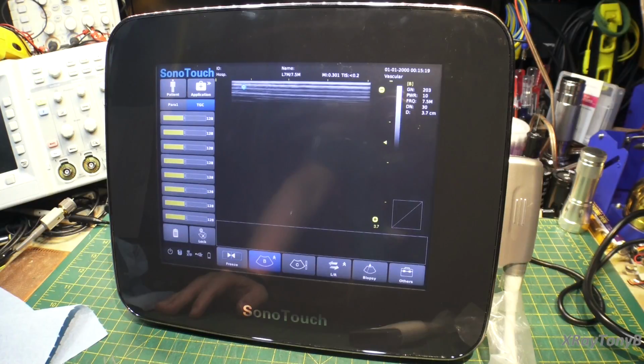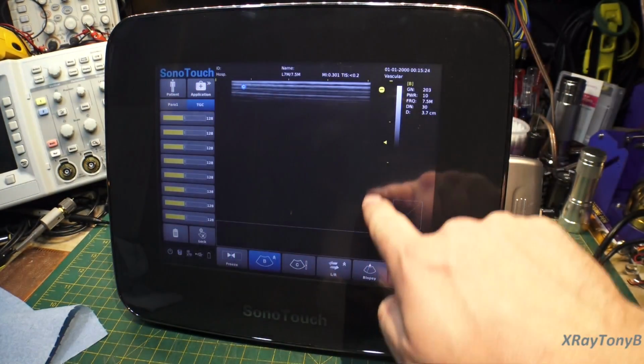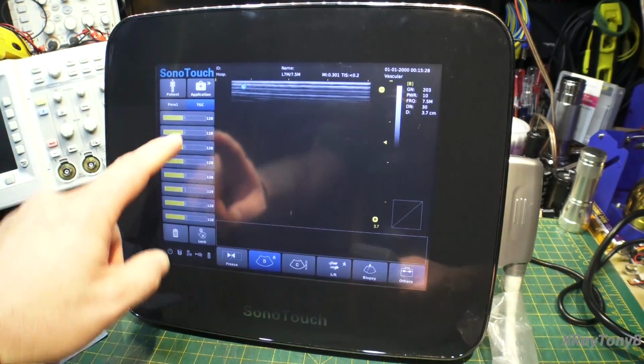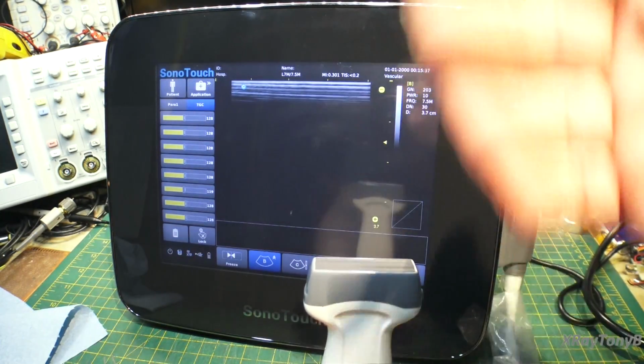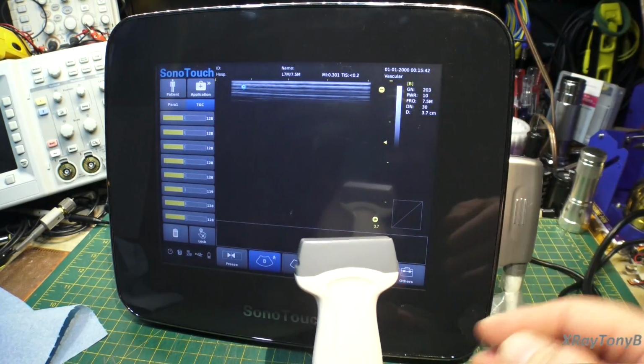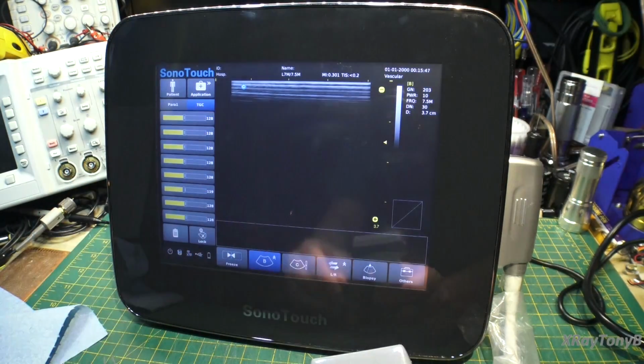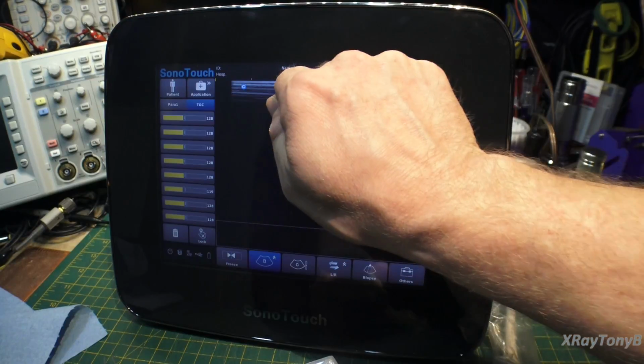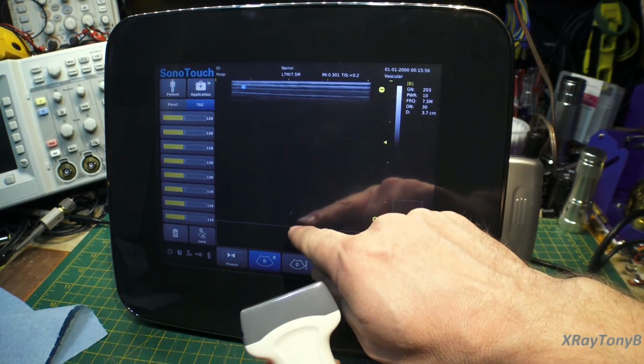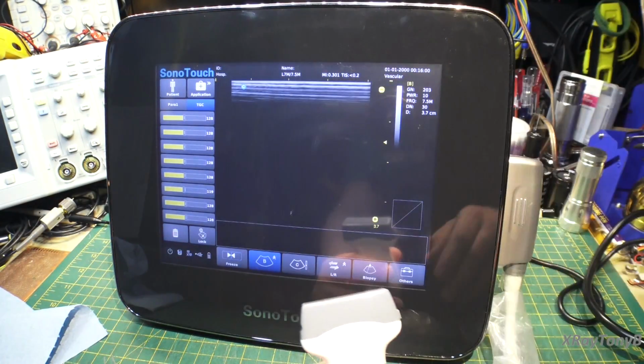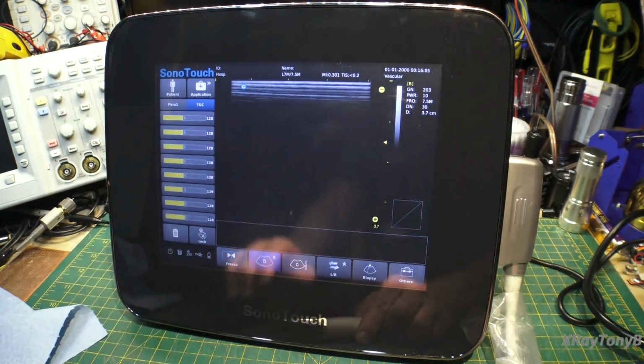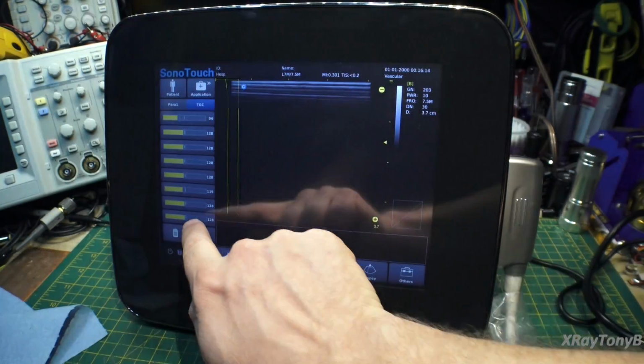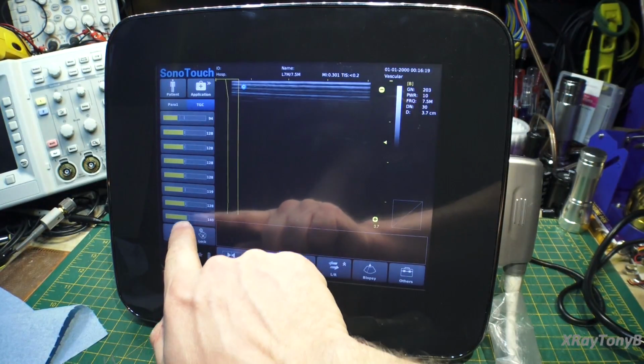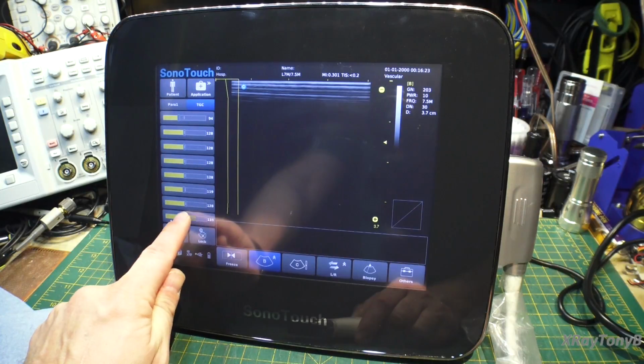Let me explain a few things here, what you're looking at. Right now, what you're looking at up here, this area is the image area. This area around here is the control area. And what you're seeing right now, these are called your TGCs. So remember, I told you that when the sound comes out of this crystal, reflects off of an object, comes back, and then causes a little current in here that's picked up and amplified. Well, these TGCs are actually little zones for how far away. So up here represents the actual transducer itself, and down here represents about this far away from the transducer. And each one of these adjusters is like a brightness control for these little focal zones. So if I turn this one up, you can see I'm brightening that area at the top. If I turn this one up, it brightens the area at the bottom, and so forth. So we can use that to fine-tune the image once you get an image on there.